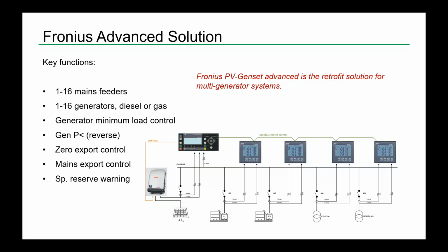In terms of spinning reserve, we don't actually handle this because, as you see, we don't control the generators. We control the PV inverters only, but since we measure all the power sources, we can give you spinning reserve warnings. So you have different levels of spinning reserve warnings, and these warnings, let's say you have less than 30% or less than 10% spinning reserve, are something you can use in your application. So maybe trip some load or start additional machinery.